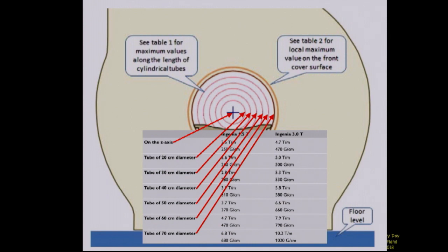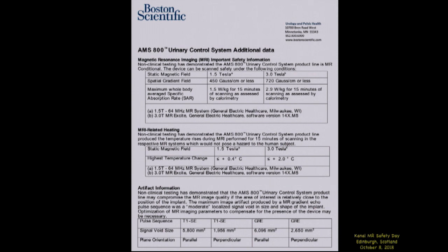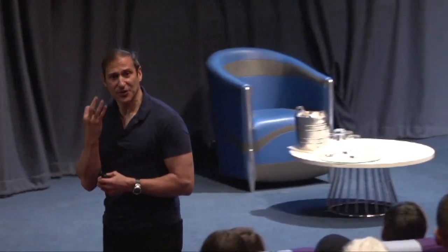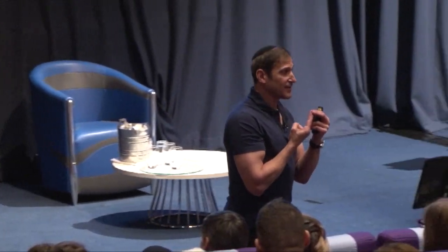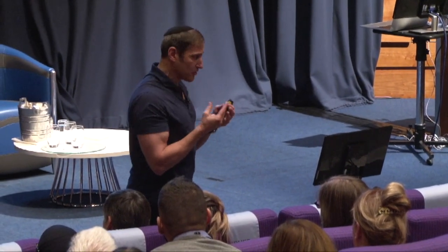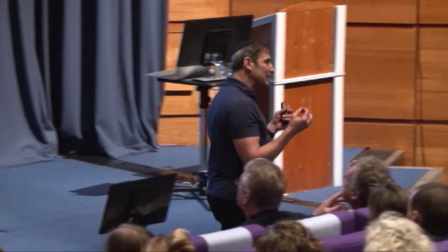So as you can see, there are different strengths in different positions radially, not just as you enter the MR scanner, but even from the center of that patient to the skin. Using one example, implants, devices can be labeled. So now, look at me before you look back there. Now you understand why when it comes to labeling implants for MRI safety, you have 3 flashlights. You have 3 different energies. One of those energies, static field, is going to break down into 2, the strength of the field and the magnetic spatial gradient. So now you understand why when they try on these labels for all of our regulatory agencies internationally, when they label, can I take this Blorg Model 300 into an MR scanner?